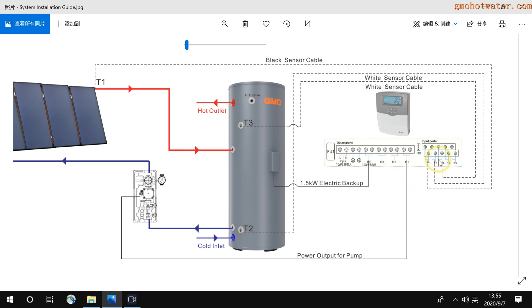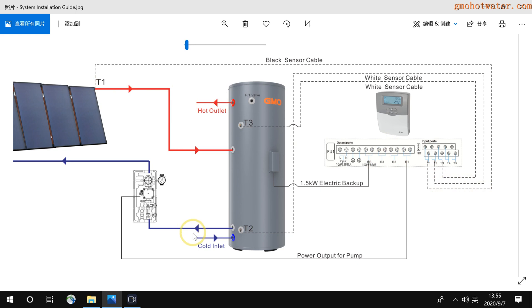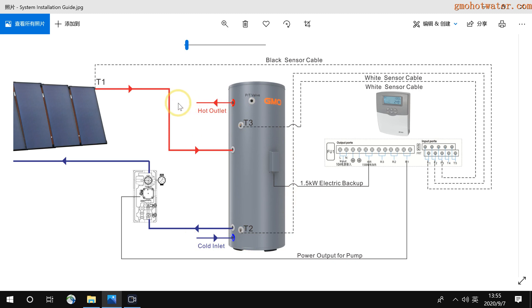So the program is, if the water in the hot outlet pipe is lower than 40 degrees Celsius, then the pump connected to R2 will circulate. So if you need to use hot outlet to the tank, you will have a circulation from hot outlet and return to the tank. In this way, it can guarantee the hot outlet pipe with hot water. This is an advanced function. You don't need to learn about it, but if you have this kind of requirement, you can study the manual in detail.